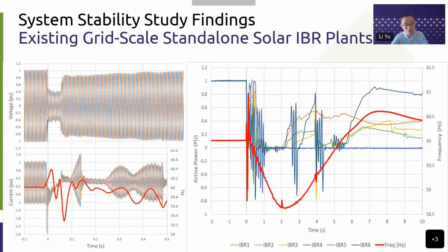This slide shows the DFR data we extracted from the system level event that happened 2 years ago. The two plots on the left-hand side show high speed recording for one specific solar IBR plant. The upper plot shows voltages, and the lower plot shows instantaneous current and the frequency. The system event happened around 0 seconds, and the fault lasted around 4 cycles, which dragged the system level voltage to around 0.4 per unit. After the fault got cleared, voltage immediately restored to 0.8 per unit, and then gradually restored to 1 per unit within 0.4 seconds.